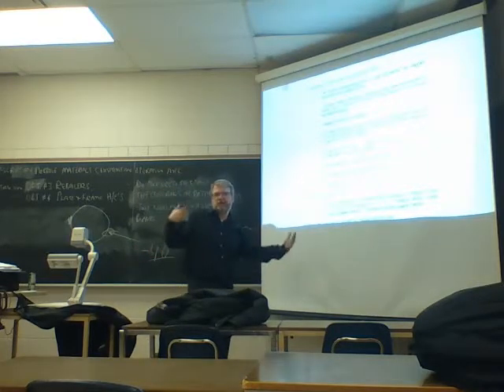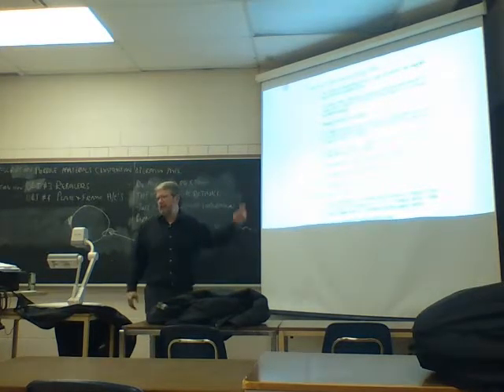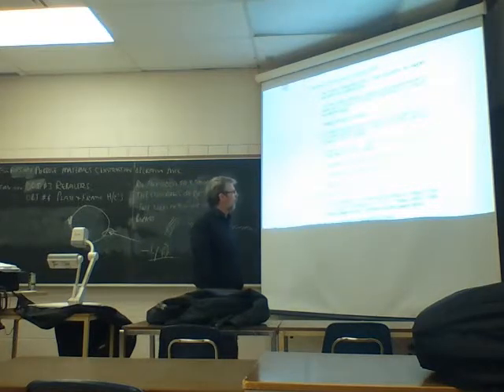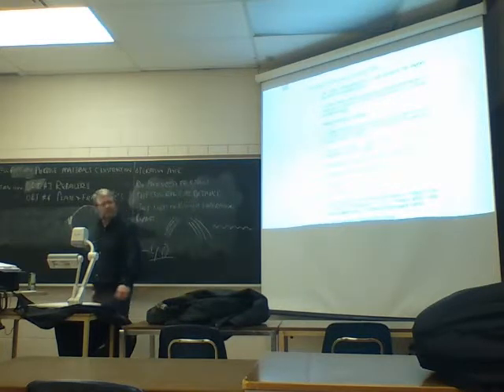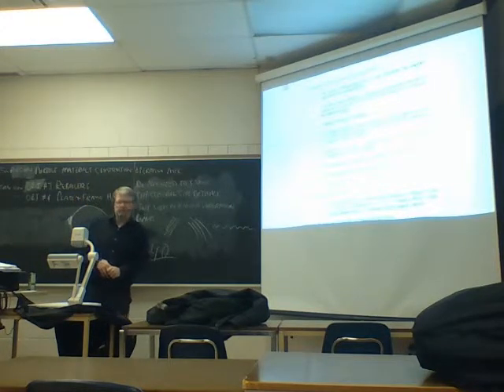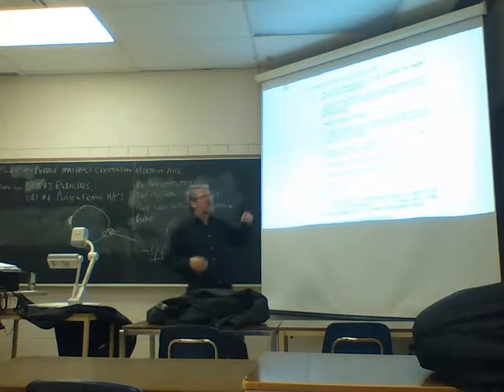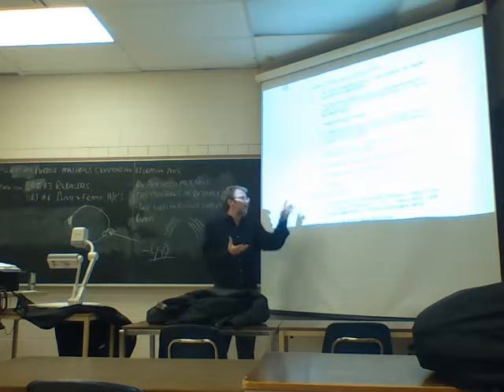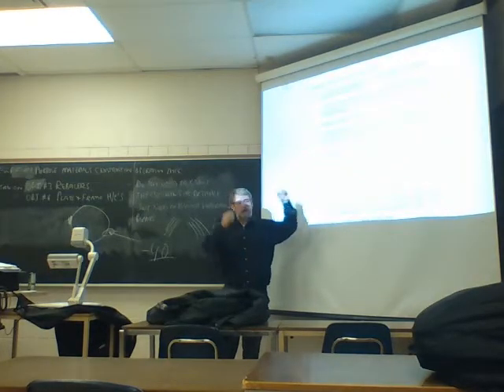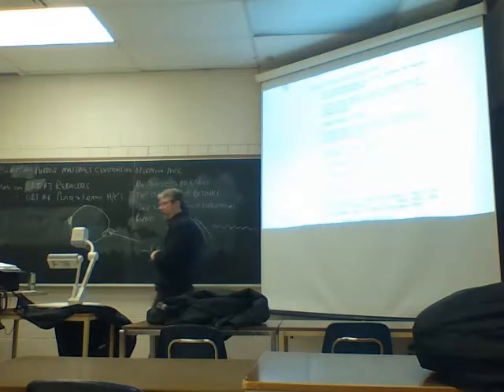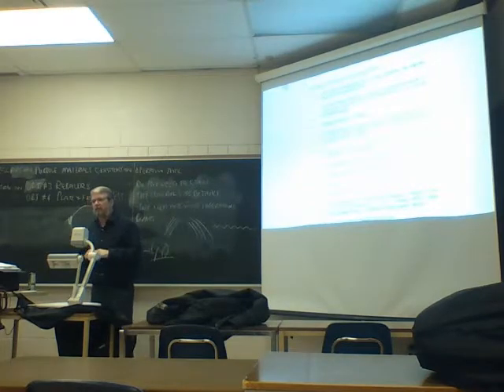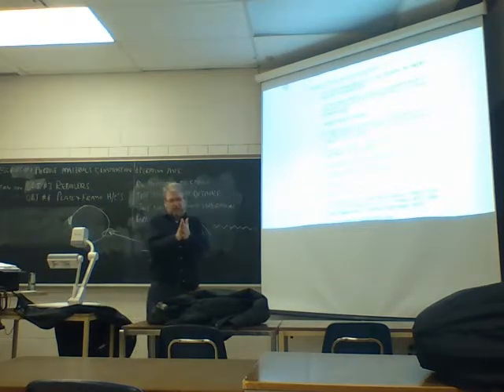Vibration free - I wouldn't touch that. What does vibration free really mean? They still do vibrate. I would say shell and tube is more susceptible to vibration than plate and frame - because you've got all those plates and gaskets, and these things vibrate like crazy, whereas shell and tube can vibrate quite a bit without issue. So I have a problem with that one.